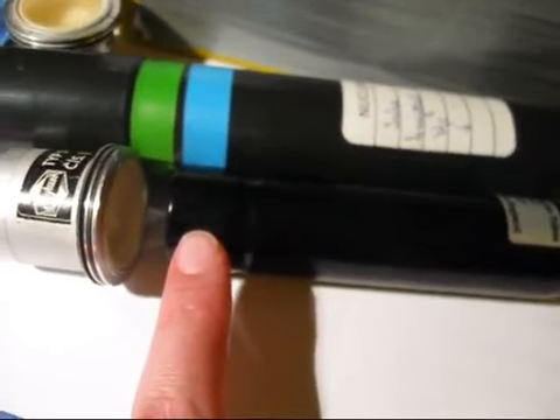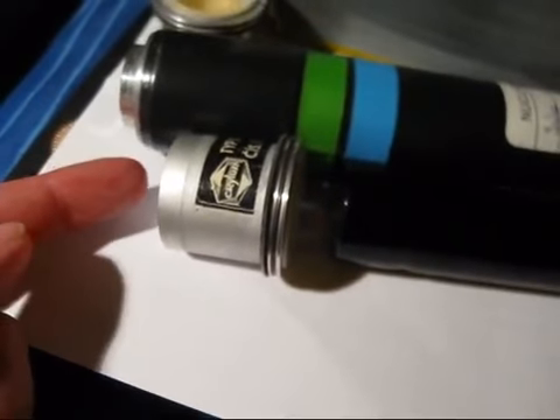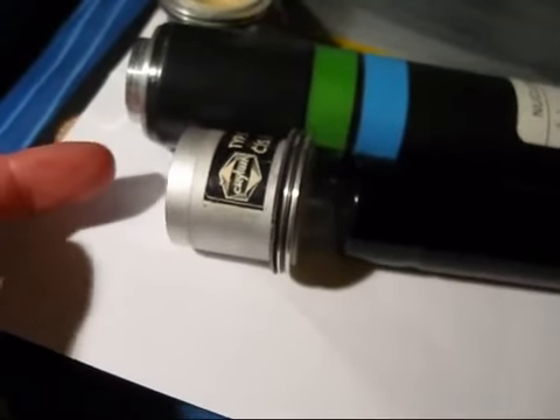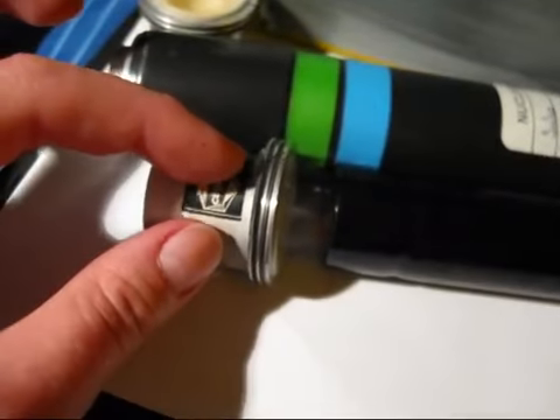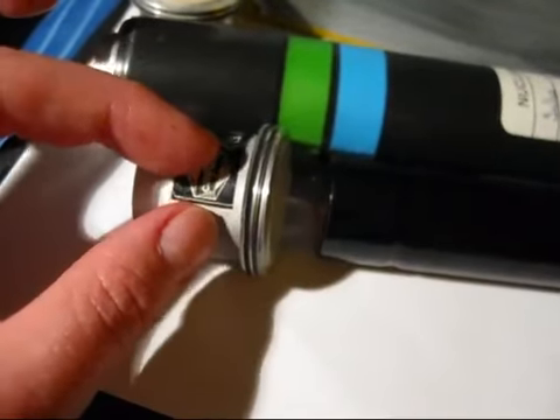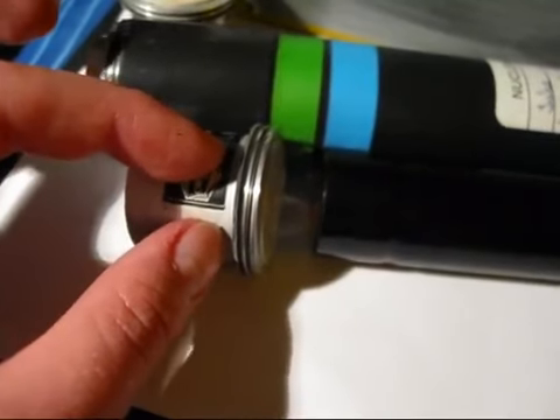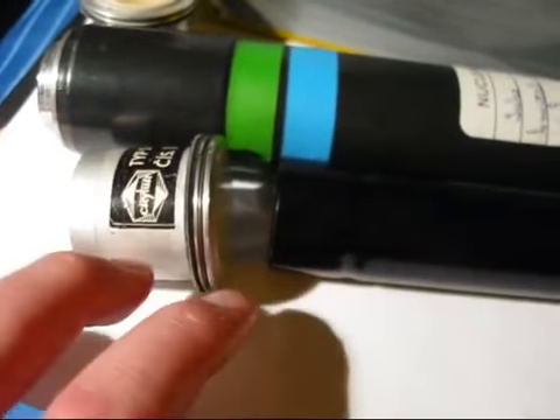That is this thing. It is all sealed up, but you can somewhat see inside maybe. You can just see reflections of the camera, but I think you should be able to somewhat see inside if you focus on that. And this device will be connected to the crystal like this. It will be fitted really tight, and there's a little photocathode in there. So what happens is that ionizing radiation, like people falsely call it radioactive radiation, enters from this side and causes little scintillations or light flashes within this sodium iodide thallium crystal.